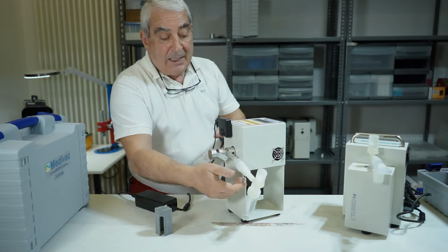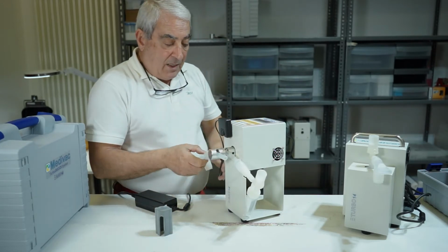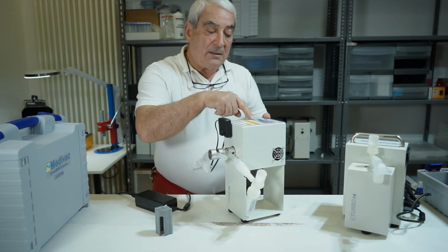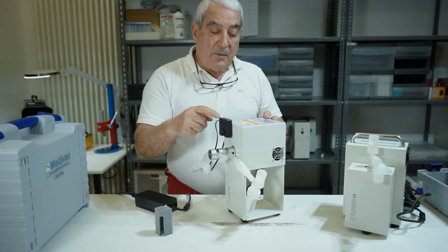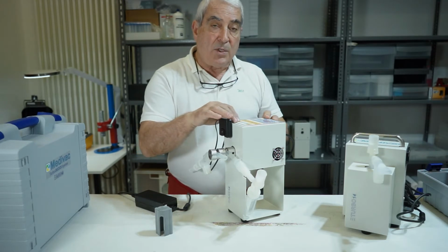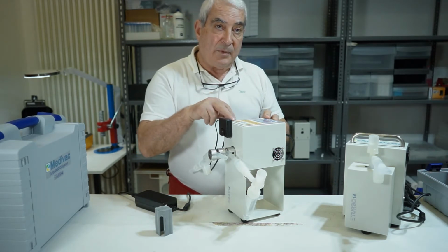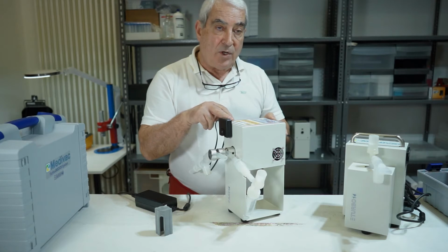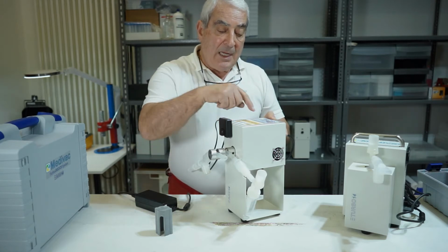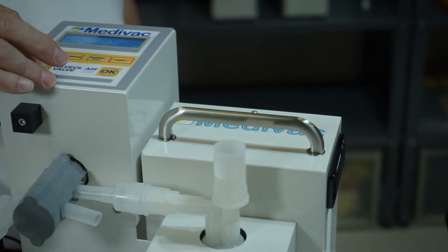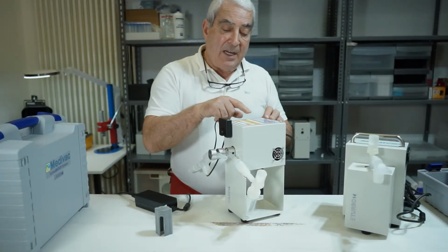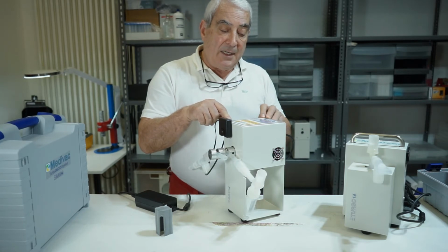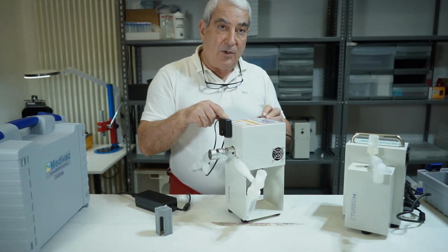The valve activation is done through the electronic circuit, following the instructions clearly described in the instruction book. The display placed in the upper part of the AAV allows us to verify the different functionalities for the activation and setting, described in the instruction booklet.